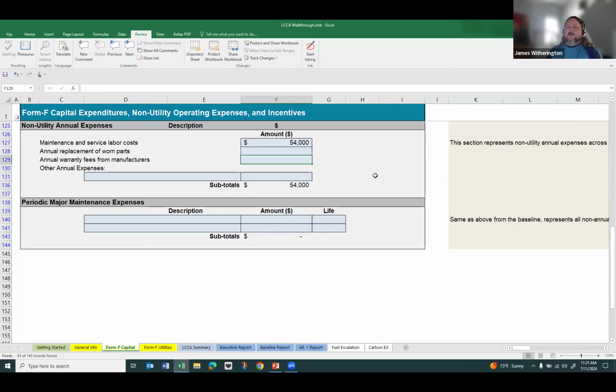When it comes to, I think what you're talking about here is the remaining useful life of the existing equipment. In Commerce, we don't have anything that dictates what that remaining useful life ought to be. That should be part of the audit evaluation as you walk through your systems and equipment to determine on site basically how long that equipment has left before it requires replacement. If you have something that's at the end or beyond its industry standard useful life, but has been well maintained and is still operating, for all intents and purposes, it's not beyond its useful life.